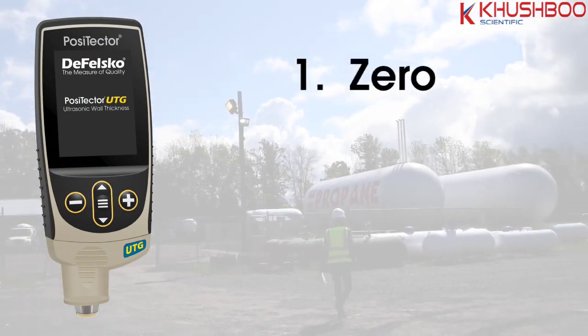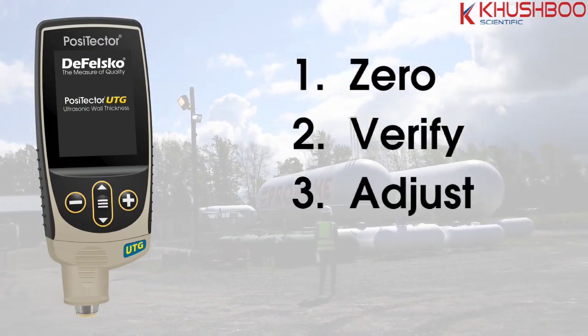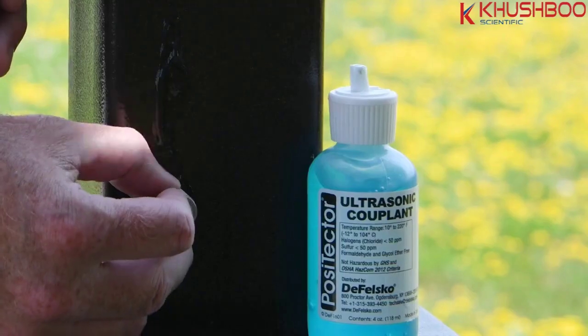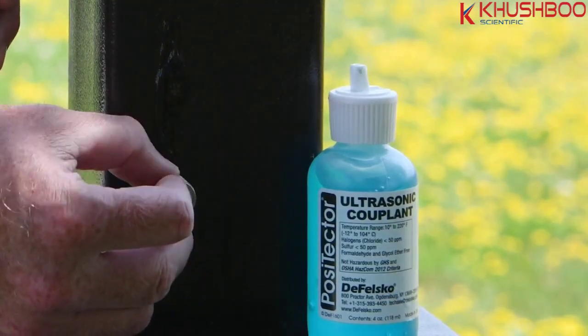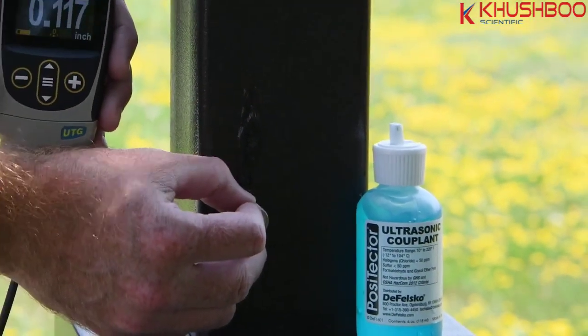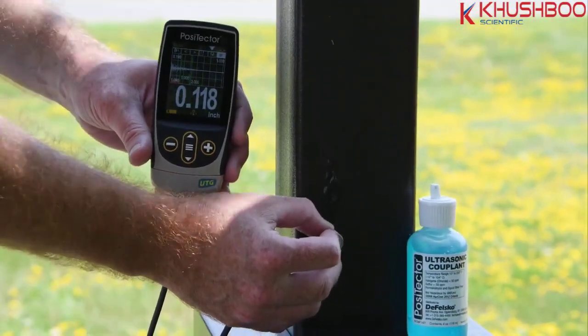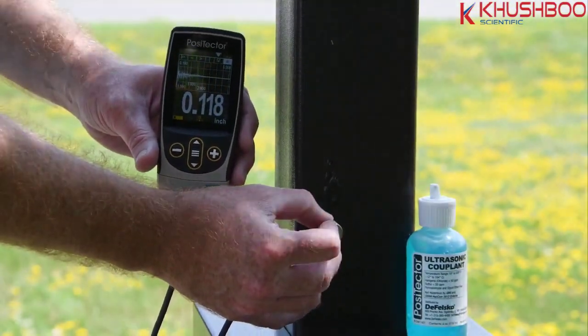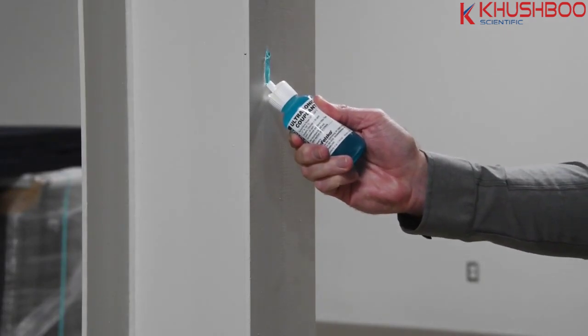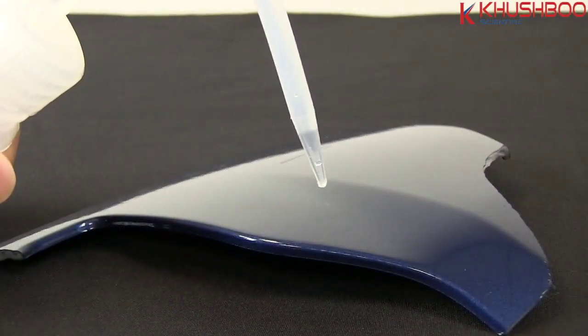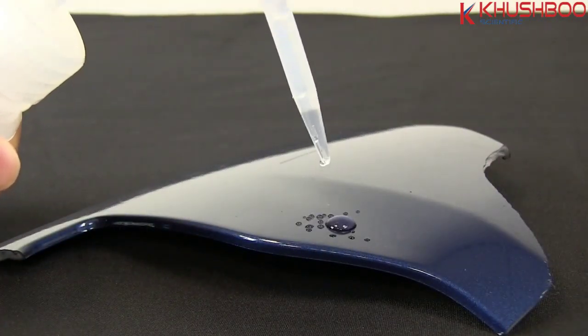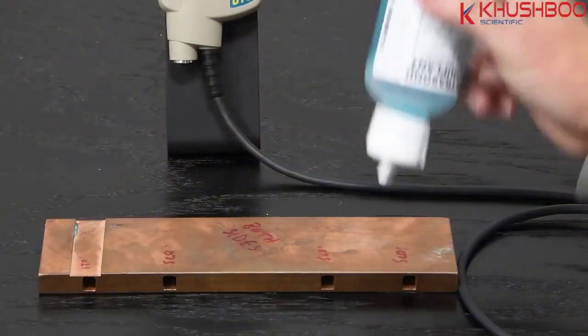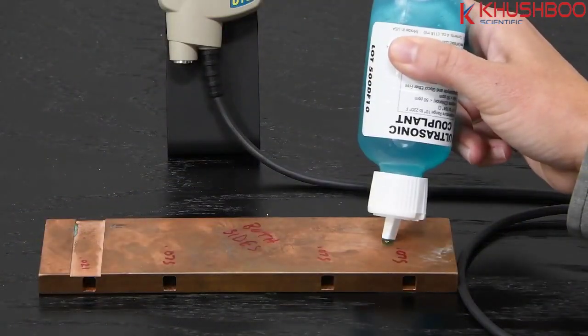Simply zero, verify, adjust, and measure. For all measurements, couplant is required to help propagate ultrasound into the coating. The included gel is ideal for rough coatings and for vertical surfaces. Alternatively, a drop of water is often sufficient for smooth coatings on horizontal surfaces. Only a small pea-sized drop is necessary.